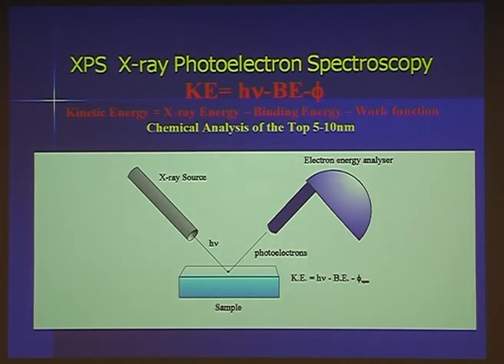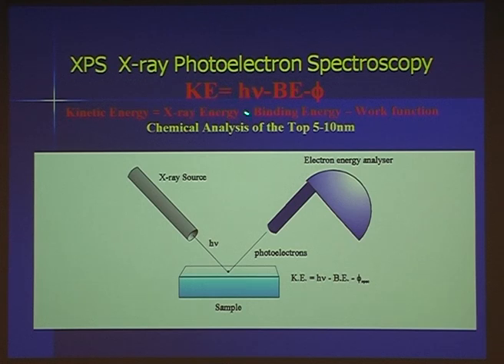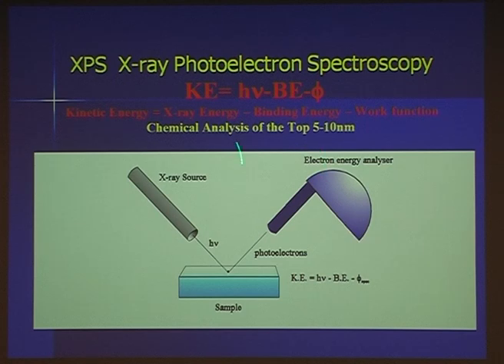Let's see how it works — a very basic process. You have an X-ray source providing the photons; they bombard the surface and knock out what we call the photoelectrons. These go up into an electron energy analyzer, and the kinetic energy of these electrons is equal to the input energy minus their binding energy. The electrons only escape from about 5 or 10 nanometers. So it's very simple: an X-ray source, a sample, and an electron energy analyzer.